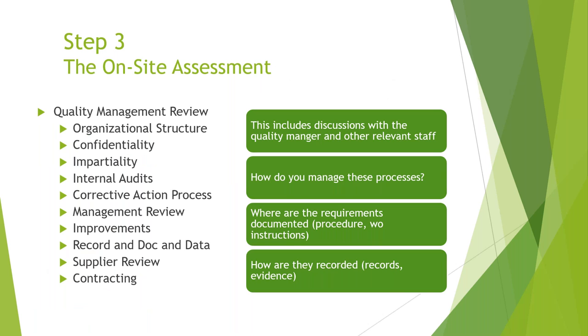The on-site assessment will be a review of your quality management system. We're going to look at your organizational structure, legal entity, how you handle confidentiality and impartiality, your internal audit process, corrective action process, did you do a management review, do you identify improvements within your laboratory, what records and documentation you have, and who your suppliers are and how you do your contracting. All these things could be part of the quality management system review and also the technical review.